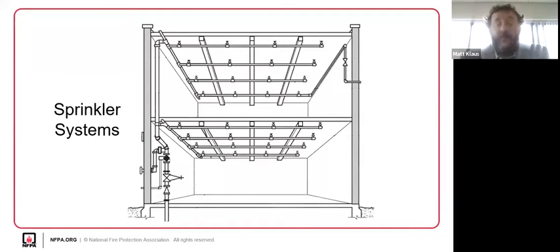We've got check valves and gate valves, and fire department connections where they can pump water in. We don't have to all become experts, but understanding matters. If we have a domestic water leak and we're running around shutting off valves, when you shut off a valve that supplies a sink and leave it closed, somebody eventually notices - hey, I'm not getting water out of that faucet. When you do it to a fire protection system, nobody ever really knows. You don't find out until the sprinkler operates and nothing comes out of it.